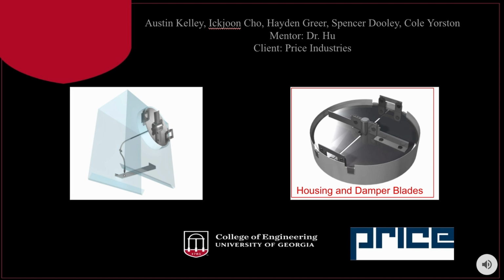The damper blades are made of in-house sheet metal and are cut in half circles, which allows them to open in a butterfly style as they pivot about a center point. This helps conserve space in the ductwork so the system does not interfere with the plenum. These blades are held within a sheet metal housing which slides onto the plenum to be used in HVAC systems around the world.